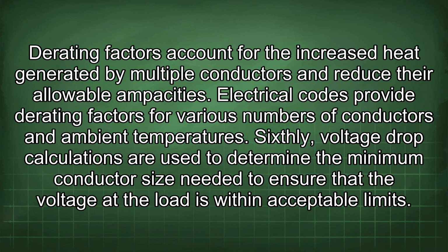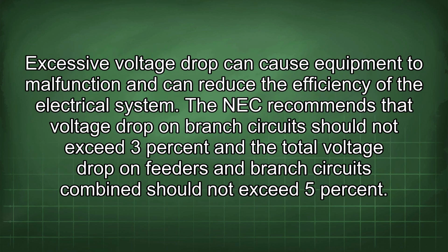Sixthly, voltage drop calculations are used to determine the minimum conductor size needed to ensure that the voltage at the load is within acceptable limits. Excessive voltage drop can cause equipment to malfunction and can reduce the efficiency of the electrical system. The NEC recommends that voltage drop on branch circuits should not exceed 3% and the total voltage drop on feeders and branch circuits combined should not exceed 5%.